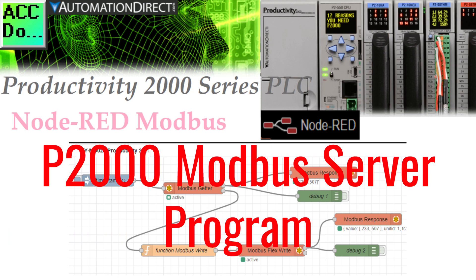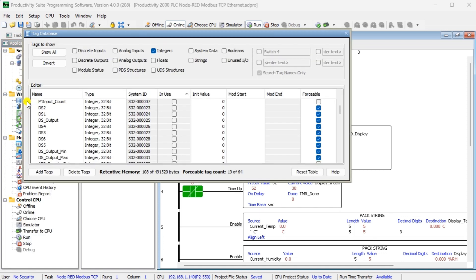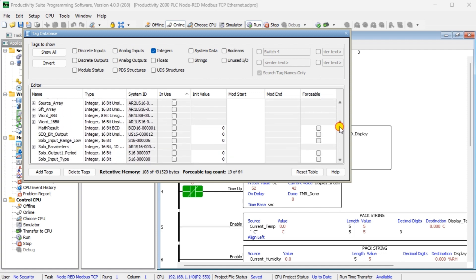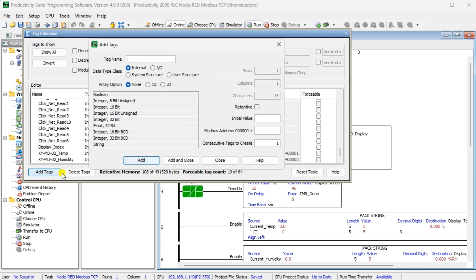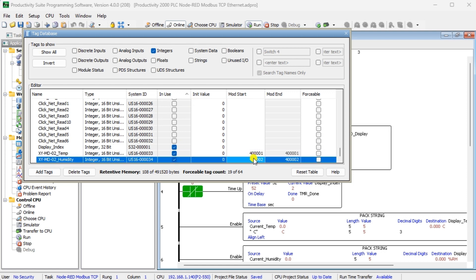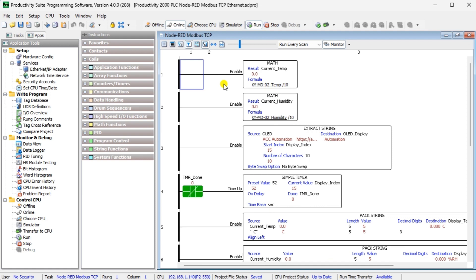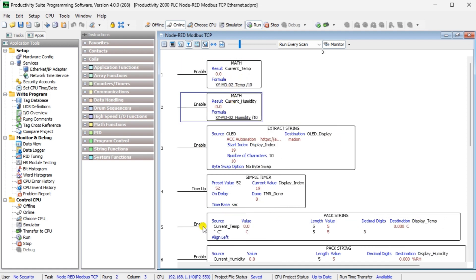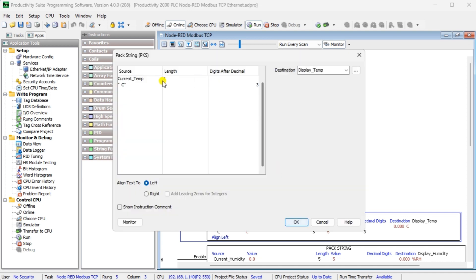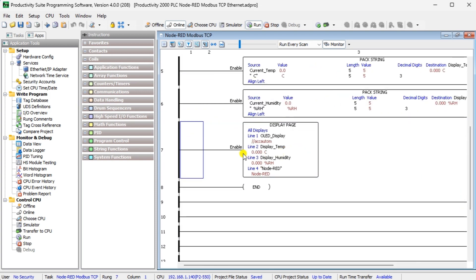P2000 Modbus server program: using the Productivity Suite programming software, we can set up our P2000 PLC to accept the Modbus values read from our XY-MD02 sensor. Display the tag database and add two more tags to store the temperature and humidity readings from the sensor. The Modbus addresses will be 4001 and 4002 for temperature and humidity respectively. Temperature and humidity sensor values will have a decimal place understood. The math instruction converts the sensor reading to a real number so it can be displayed on our P2000 CPU.